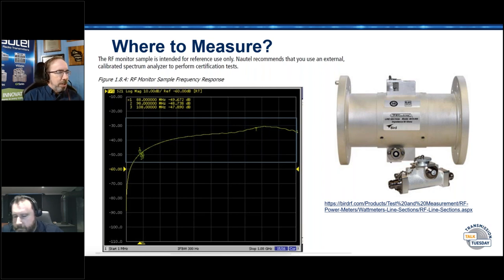So for that, again, antenna—a line section like the Bird one I've got shown on the right. Here's the other thing: if you've got a sample element with your line section, the sample element and the line section need to be calibrated together. If you send them into Bird for some nominal fee, they'll send them back with an actual calibration curve, similar to what we've got here, but quite a bit more precise. Ron mentions that the Bird sample ports are all characterized for each frequency range and line section size. So it goes back to the first question we had in the advanced questions—not just the measuring device, the spectrum analyzer, needs to be calibrated, but the line section or whatever sample port you're using, you've got to have the correction data for it as well.